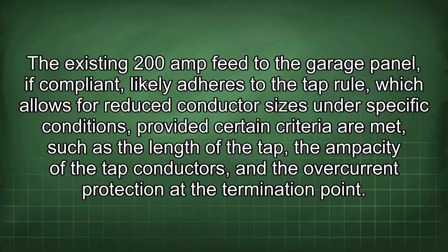The existing 200 amp feed to the garage panel, if compliant, likely adheres to the tap rule, which allows for reduced conductor sizes under specific conditions, provided certain criteria are met, such as the length of the tap, the ampacity of the tap conductors, and the overcurrent protection at the termination point.